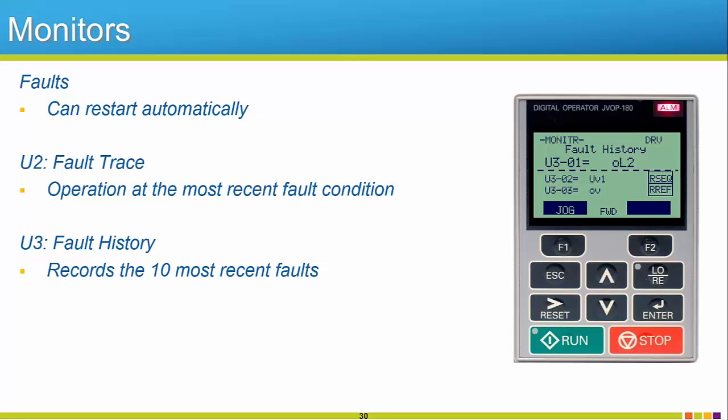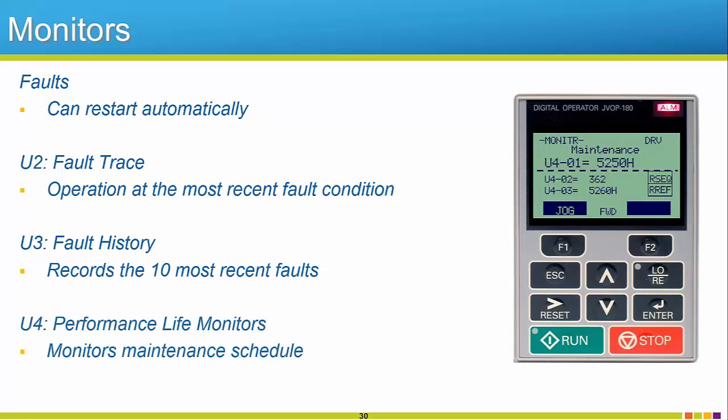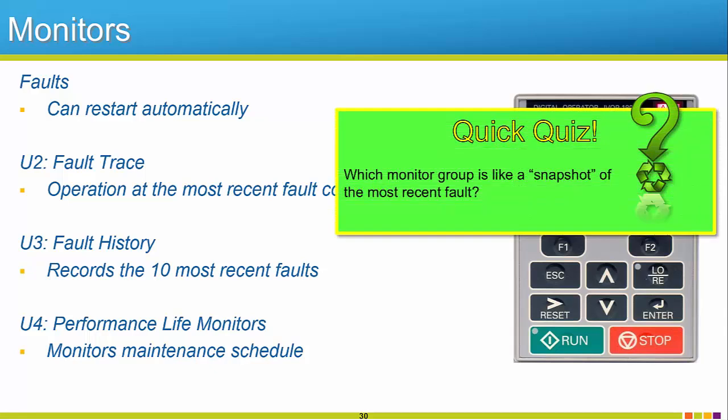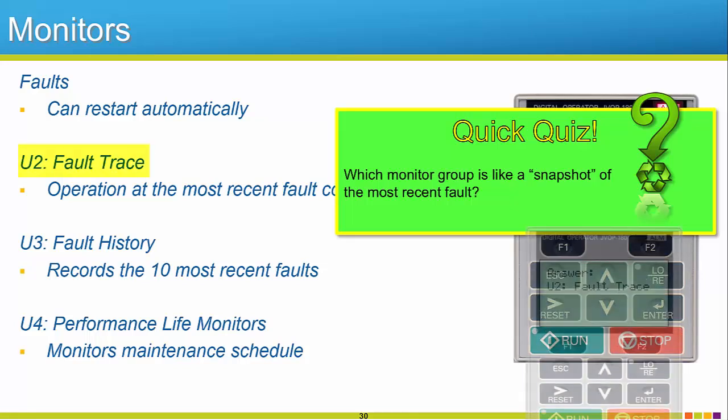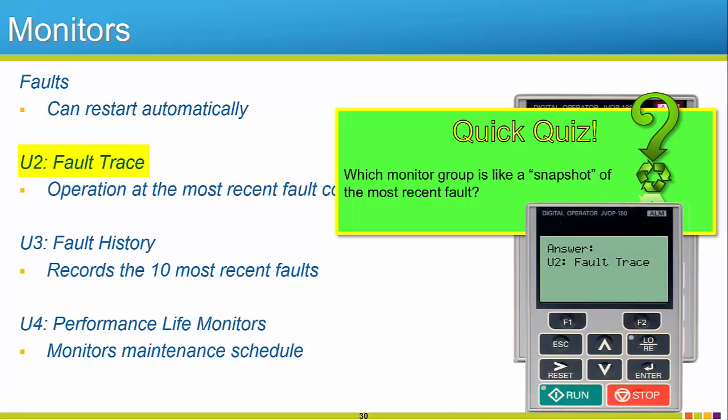The R1000's internal components are tied to yet another set of monitors, the U4 performance life monitors. These display what percentage of the estimated life of each component has been used. Once a certain level is reached, the keypad will give you a friendly reminder that preventative maintenance is recommended for the aging component. Quick quiz time. Which monitor group is like a snapshot of the most recent fault? The answer is the U2 fault trace group. The fault trace group can be described as a picture or a snapshot that was taken when the unit faults out. This snapshot stores key operation monitors so that the unit's troubleshooting can be done more efficiently.